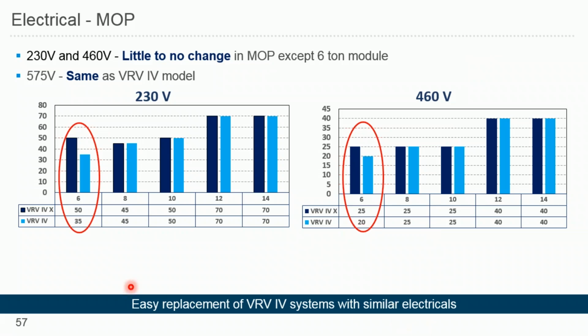And keep in mind that for multi-module configuration, the 6-ton model will not be used. So it's going to be all 8, 10, 12, 14-ton models. So multi-module electricals will not be changing compared to VRV4 electricals as well.